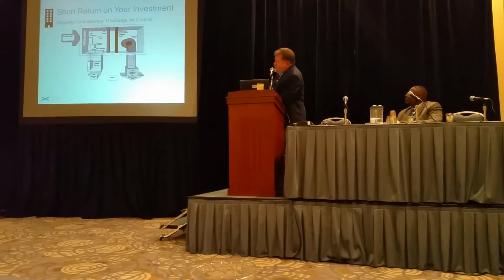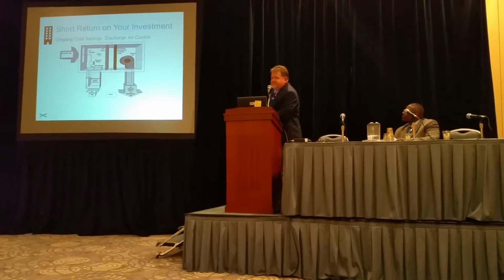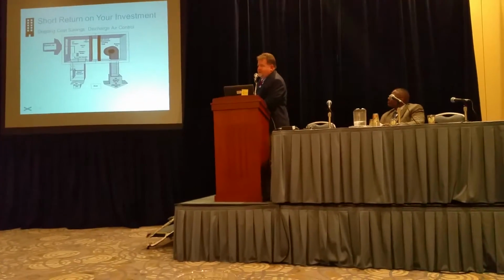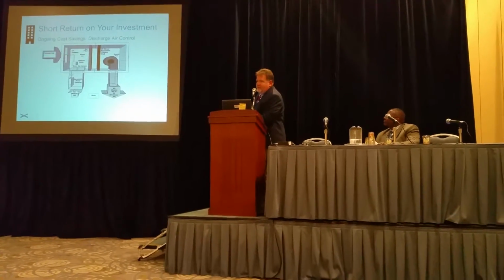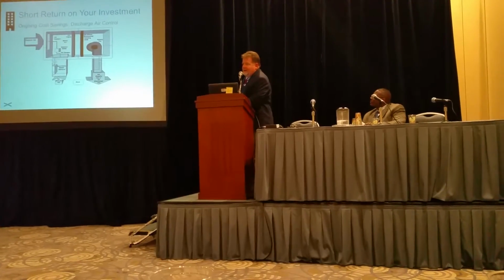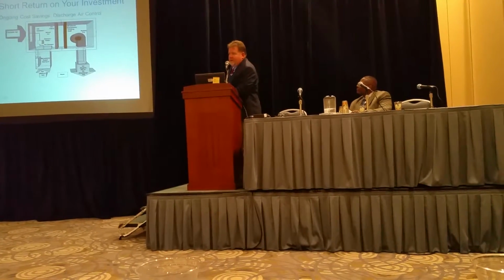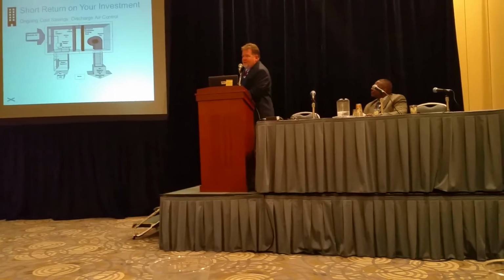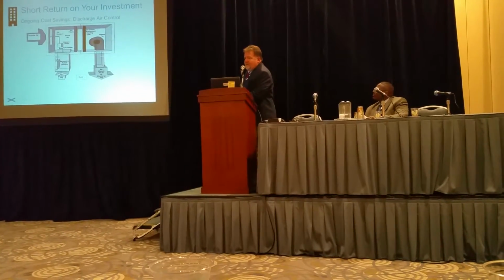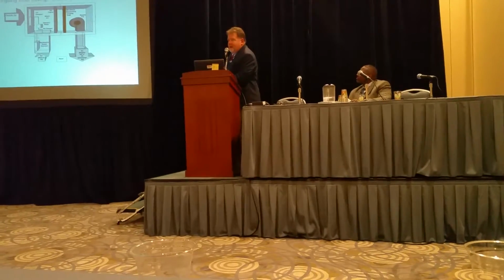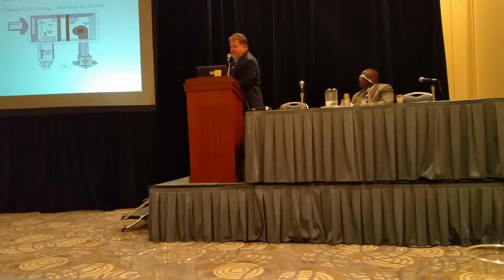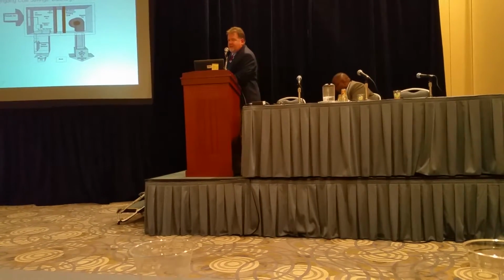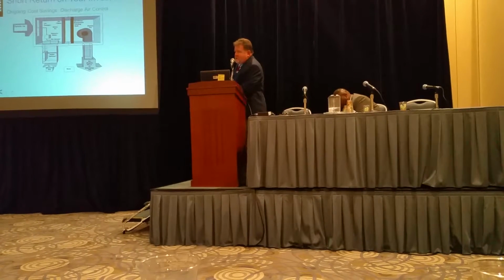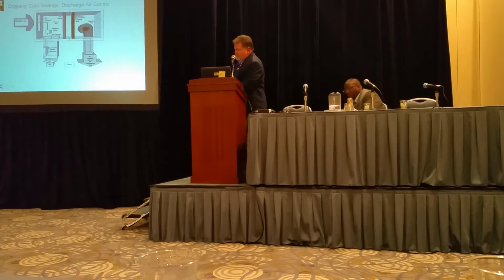Discharge air control, it's important. If your air handlers are putting out too cold of a temperature because you can't control it, all of a sudden your reheat coils are turning on to heat up the space because it just got too cold. Surprisingly enough, it's a real quick formula: BTUs per CFM multiplied by how many degrees of control will tell you exactly what we're saving. So tight discharge air control, very, very important.